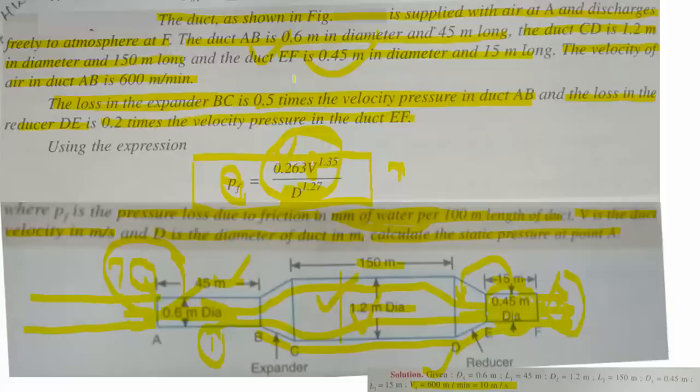Pressure loss in reducer DE equals 0.2 times the velocity pressure head in EF section. The velocity pressure head in EF is 19.4 mm of water. So loss in DE = 0.2 × 19.4 = 3.88 mm of water. Losses in BC and DE sections are both completed.